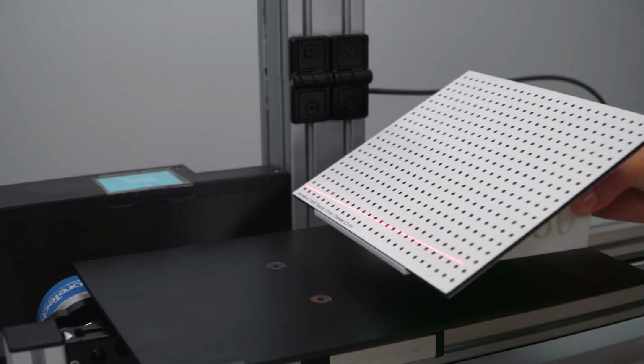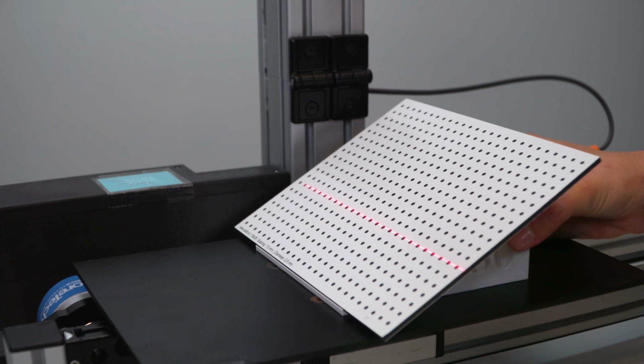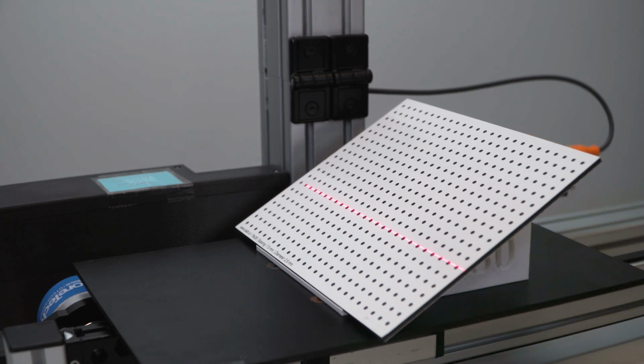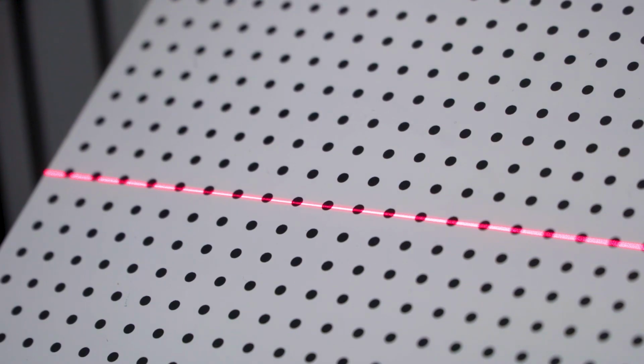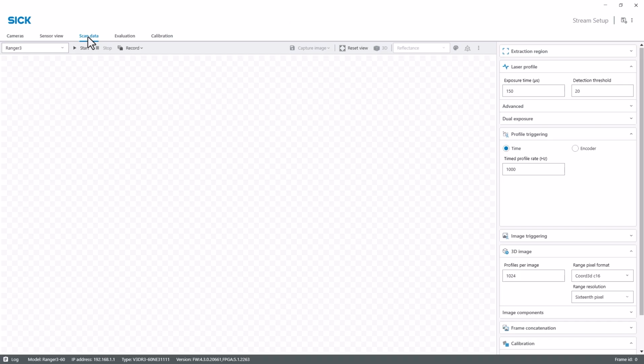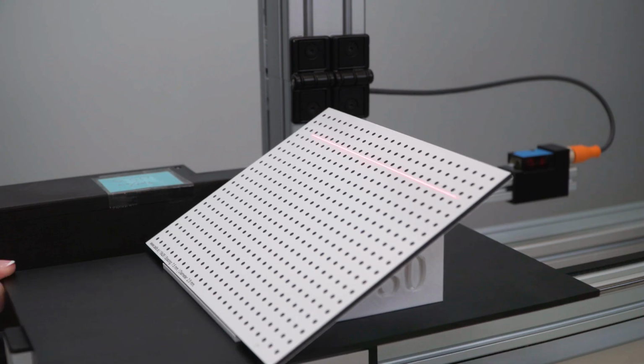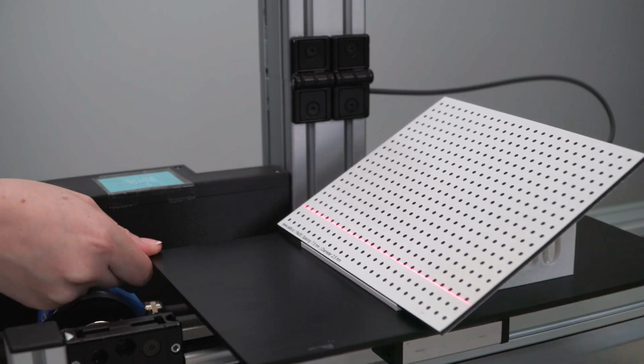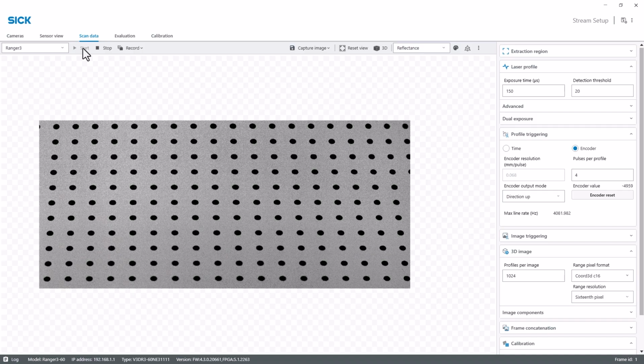Place the Dotwedge target so it's angled away from the camera to avoid reflections. It is important that the dots are aligned with the laser line. In Stream Setup, go to the Scan Data tab, and under Profile Triggering, ensure that Encoder is enabled. Make a scan and check the reflectance image to confirm that the dots are clearly visible, and then save the image for calibration.